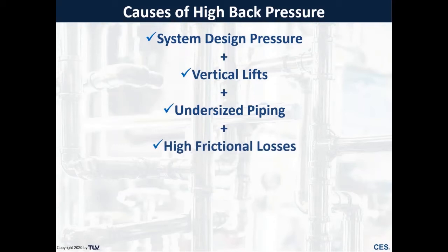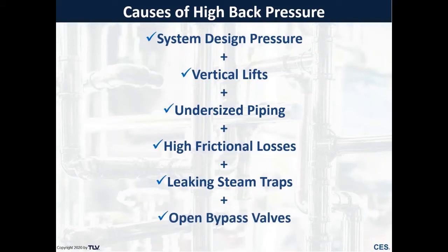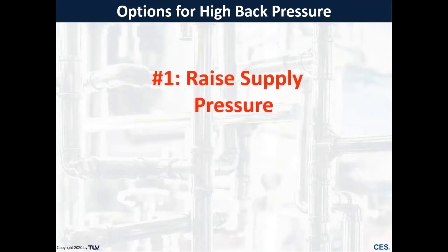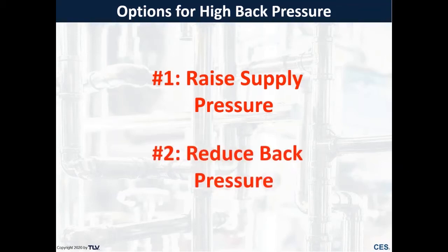High friction losses from valves, turns, and elbows also contribute to back pressure. Some big causes are leaking steam traps adding extra steam into the condensate return line, as well as open bypass valves. To address high back pressure, you have two options: raise the supply pressure — often not feasible — or reduce the back pressure. The easiest way is to replace leaking steam traps and identify and close open bypass valves, which can very quickly and easily reduce back pressure in the condensate return system.